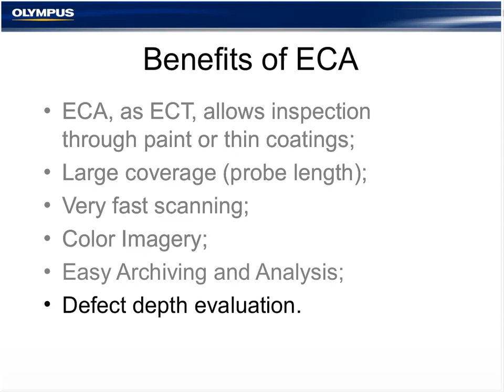Now, this section is about the SCC process pipe ECA solution, specific to that solution. It is using the OmniScan MX with the ECA module, the eddy current array module, the blue one, with new software that we just released. Olympus put that on the website as of October the 1st of this year, and it's very different in some ways because it's so much easier to use. It can be used like conventional eddy current testing. People typically don't believe how easy it is when they realize it can be operated just like a Nortec 500 and do eddy current array scans with it.